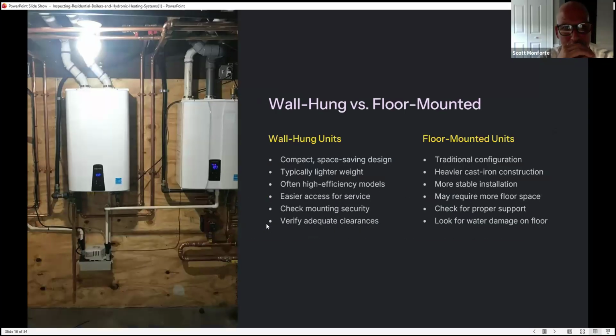Correct. Wall hung versus floor mounted. Wall hung units have compact sizes, so they're a space-saving design, typically lighter weight, often high efficiency models, and easier to access for service. Then you want to verify adequate clearances. Floor mounted units are the traditional configuration, with heavier cast iron construction and more stable installation, but may require more floor space. You want to check for proper support and look for water damage on the floor. Also on the wall hungs, you want to check for mounting security.